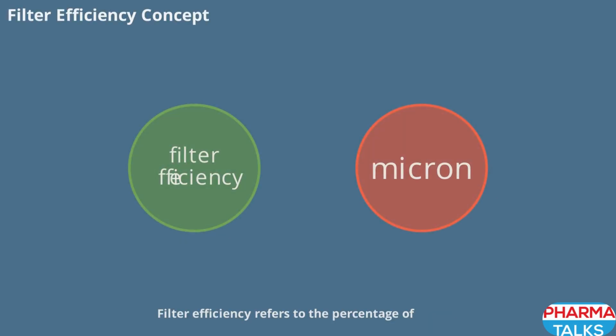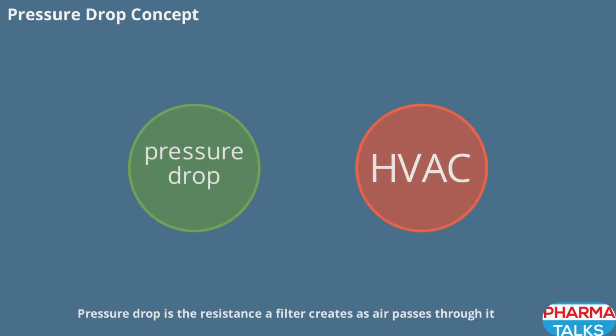Filter efficiency refers to the percentage of particles a filter can remove from the air. HEPA filters are rated at 99.97% efficiency for 0.3 micron particles, while ULPA filters achieve 99.9995% efficiency at 0.12 microns. Understanding efficiency ratings is crucial for selecting the right filter for your cleanroom application. Pressure drop is the resistance a filter creates as air passes through it. ULPA filters have a higher pressure drop than HEPA filters, which means they require more powerful fans and increase energy consumption. Managing pressure drop is a key consideration in HVAC system design for cleanrooms.